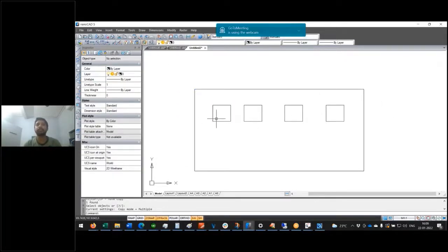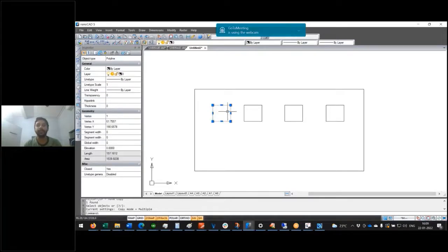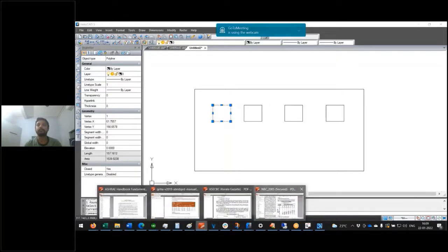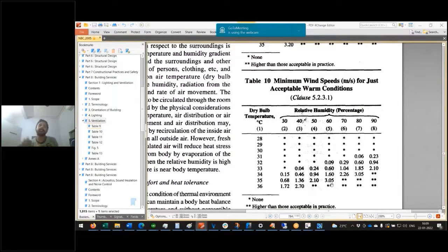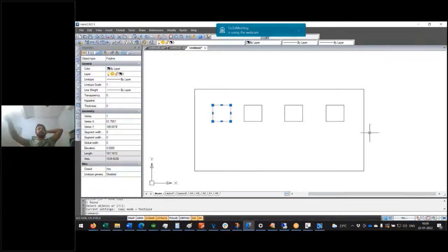So you have 4. Multiply this area in square meters by 3 meters per second. So you will get meter cubed per second. That's your flow volume that you want. Accordingly, you have to select that ventilation fan, and you will get the quantity of air. The volume of the room you already know. So you will get the desirable things. I hope that answers the question.